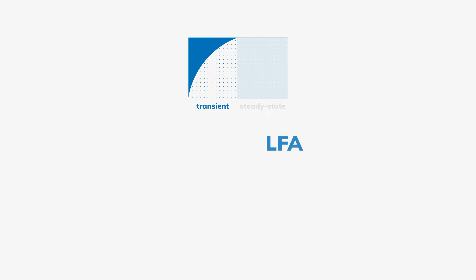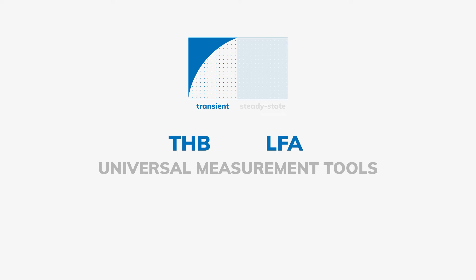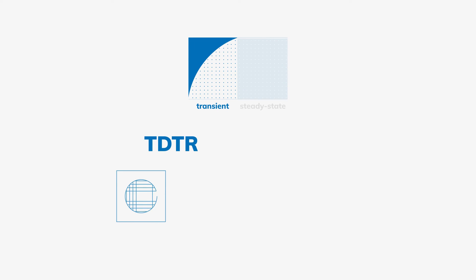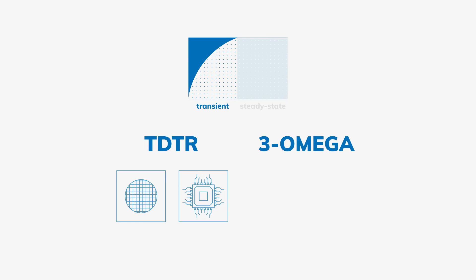The laser flash and transient hot bridge methods are universal measurement tools. The THB is used mainly for manual measurements and temperatures up to 200 degrees Celsius. The laser flash method is designed primarily for automated measurements and high-temperature tests up to 2,800 degrees Celsius. The TDTR method can be used on silicon wafers to develop high-performance computer chips. The three omega method is used, for instance, for organic semiconductors in liquid form to produce printable circuits or solar cells.